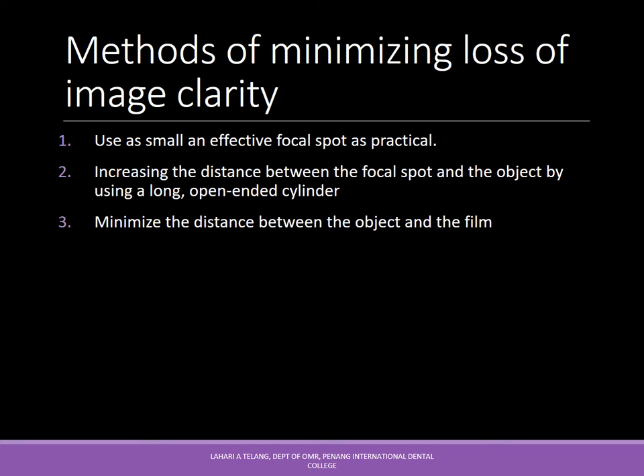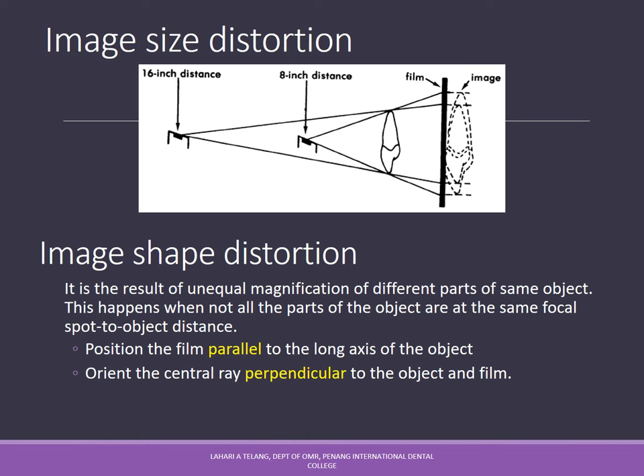To minimize loss of image clarity, use a small effective focal spot, increase the distance between the focal spot and the object by using long open-ended cylinders for x-rays, and minimize the distance between object and film. To avoid image size distortion, maintain a distance of at least 8 to 16 inches between the x-ray source and the object/film. To reduce image shape distortion — which results from unequal magnification when different parts of the object are at different focal-spot-to-object distances — the film should be parallel to the long axis of the object and the central ray should be perpendicular to both object and film.